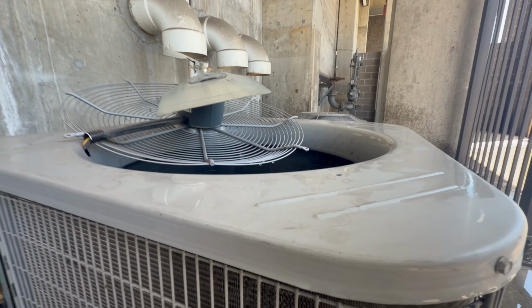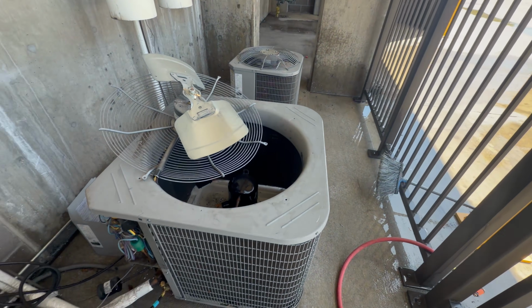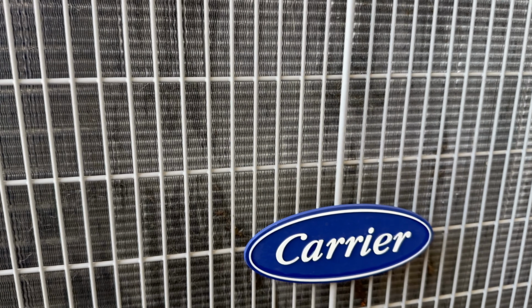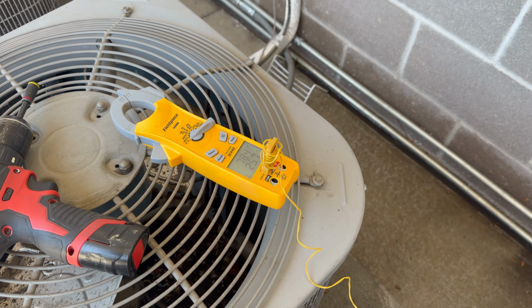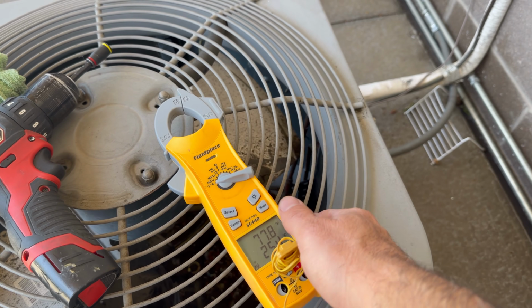Right, we got her all cleaned up, and compared to before, you can now see the fins, and we are 100% clear all the way around. Now I'm gonna wrap this hose up, put everything back together, which should take about 10 minutes to clean up, and then we'll start the unit, let that run for about another 10 minutes. I want to get as close as possible to the indoor load we had prior so we can compare pressures and temperatures. It's been about 15 minutes.